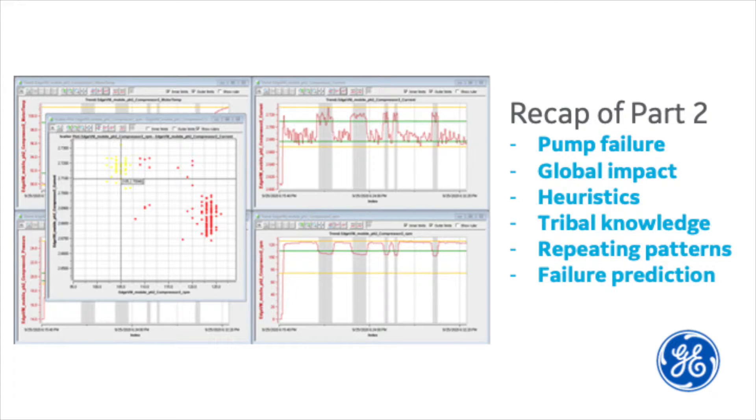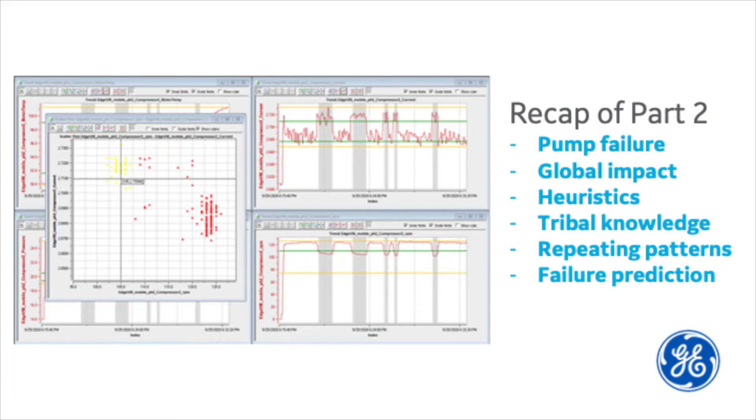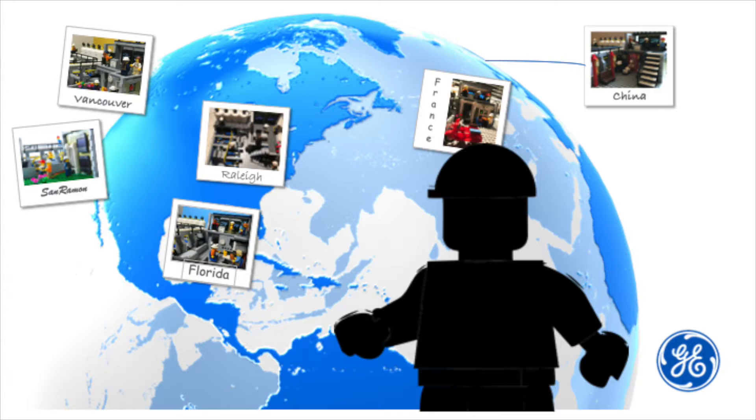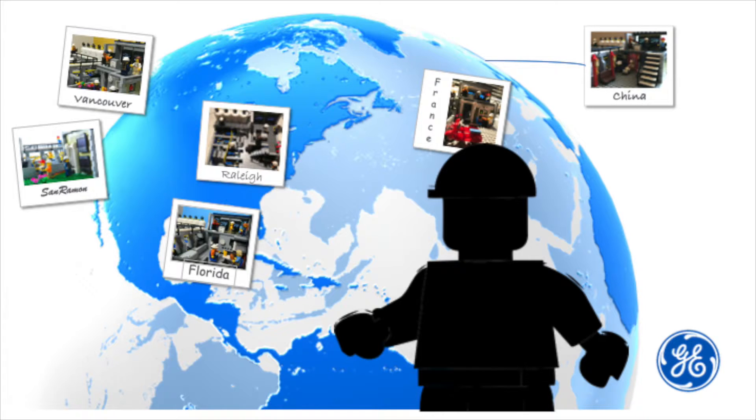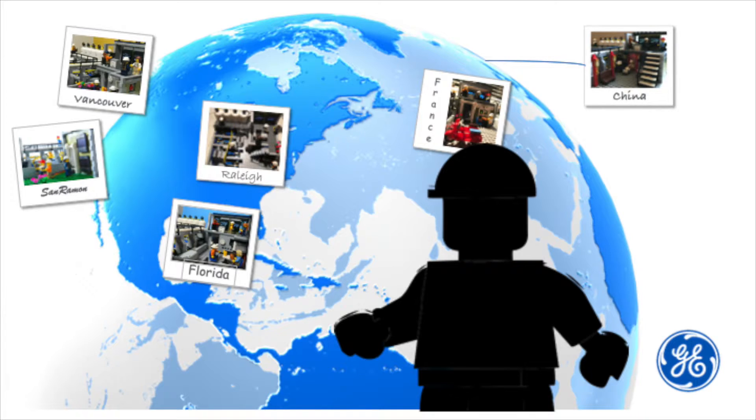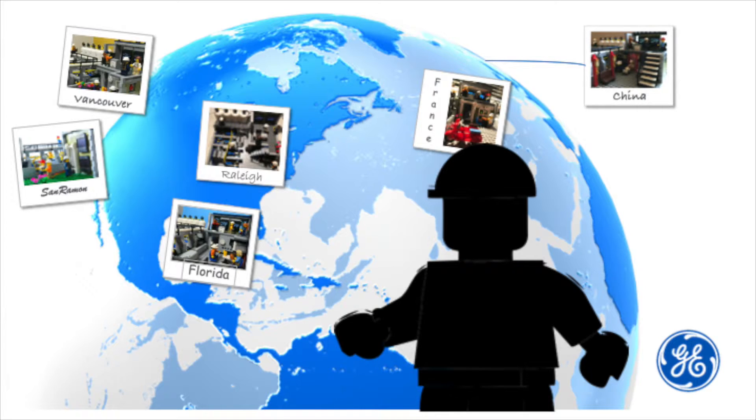With Proficy CSense, the team was able to match those heuristics to repeating patterns in the data set, revealing an early predictor of the pump failure. The very next step was for us to replicate this analysis at all the other plants. All we had to do was take a look at the maintenance records to identify when failures occurred, and then simply go find the corresponding times in the historian for each set of the pump tags. What we found was very interesting.